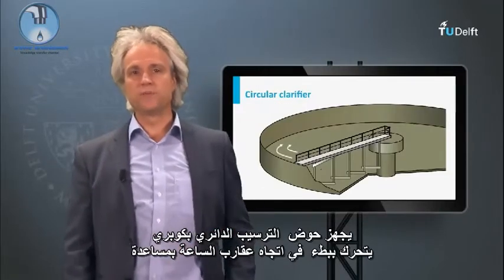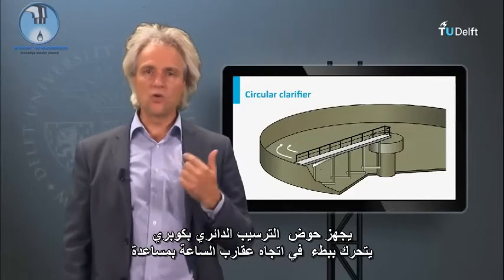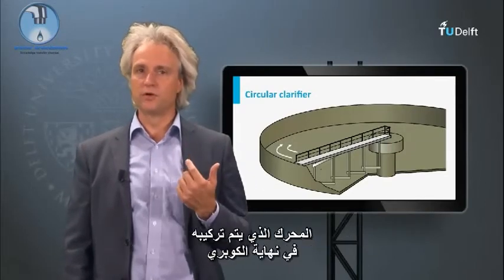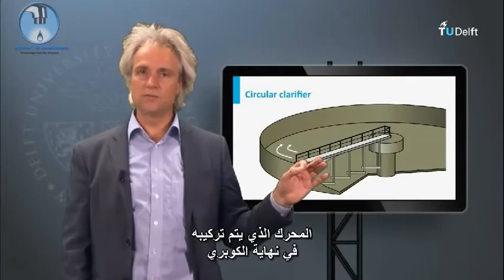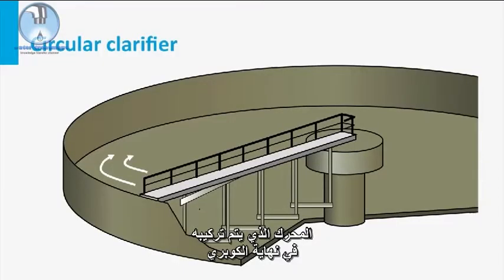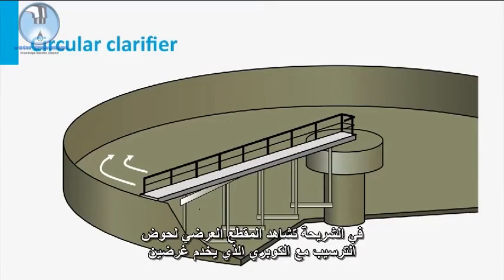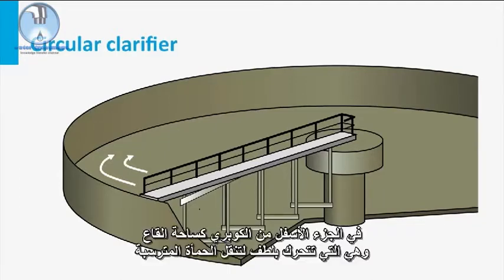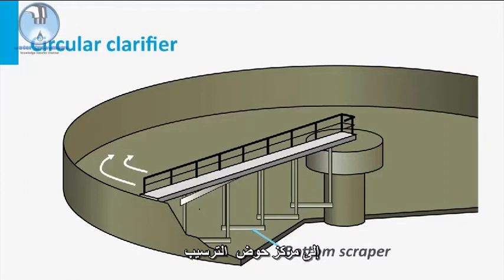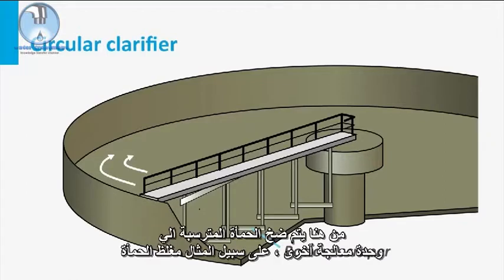A circular clarifier is equipped with a bridge that moves slowly clockwise with the help of a motor, which is mounted at the extremity of the bridge. You see a cross-section of the clarifier with the bridge serving two purposes. At the lower part of the bridge, a bottom scraper is mounted that gently moves the settled solids to the central core of the clarifier. From here, the settled sludge is pumped to another treatment device, for instance, a sludge thickener.